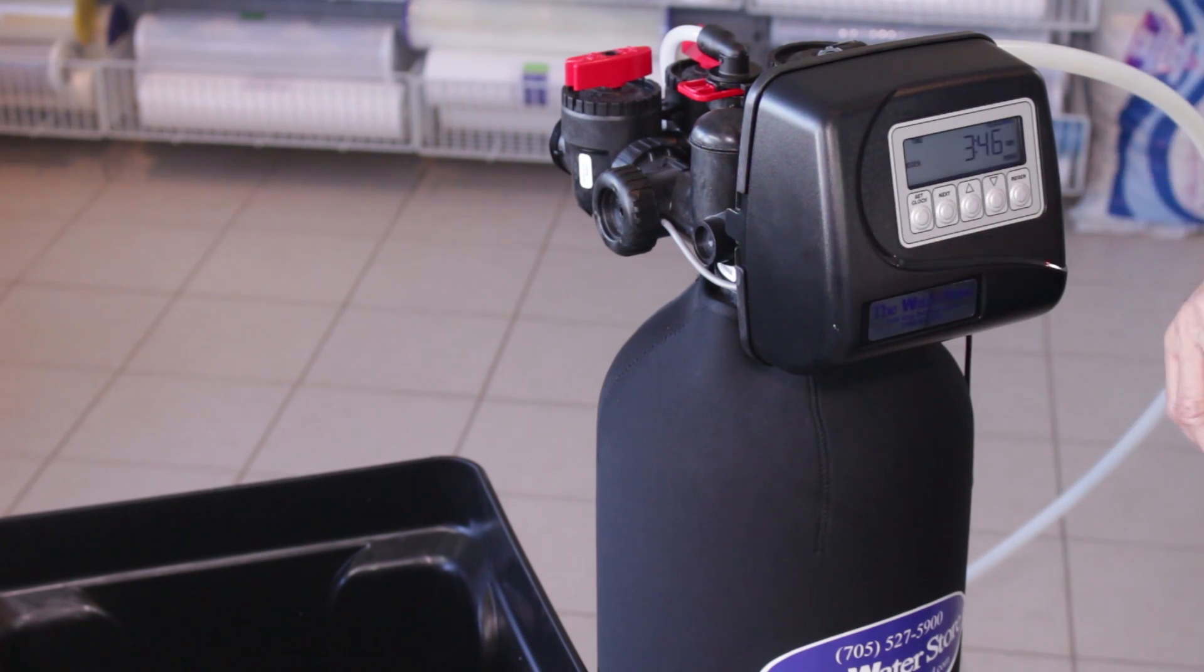So we'd let it run at this stage for about two or three minutes rinsing and again watch the drain line, make sure the water is relatively clear running to the drain. There shouldn't be any more fines coming from the media at this point and once that's happened for two or three minutes, press regen again.